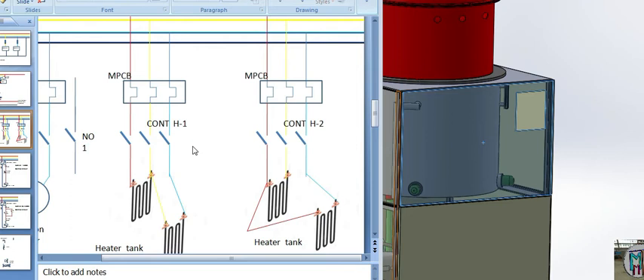Two contactors with one relay. We will fix one relay for two contactors. So when the relay is operated, at that time both contactors will start. Suppose the heater on this side is damaged, at that time we can switch off this MPCB, and we can remove this heater, and your machine will not go into breakdown.